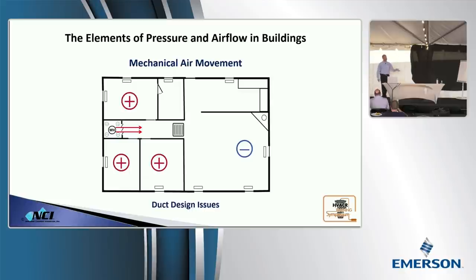They will pull the air right out of the flue. Now you may say, well, what's to keep it from coming out of the combustion air duct? It may pull out of the combustion air duct too. We don't know. Because what's on top of that water heater that allows it to communicate with the house and any pressure changes that it has? A draft hood. That water heater's got a draft hood on it. It is not a sealed system. It communicates with any pressure change inside that house.